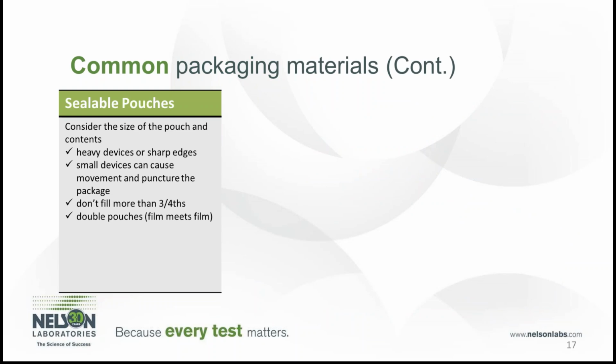Are you looking at a foil combination, or a Tyvek Mylar medical grade paper, poly? So those are all things to consider as well. Also, with the aseptic presentation, you've got heat sealable, you also have adhesive. So looking at what's going to be the best for your product, for your end use, and that aseptic presentation.